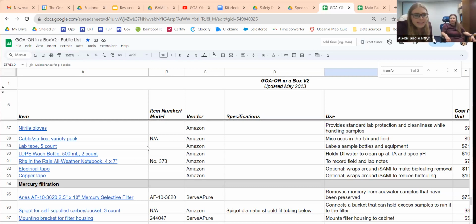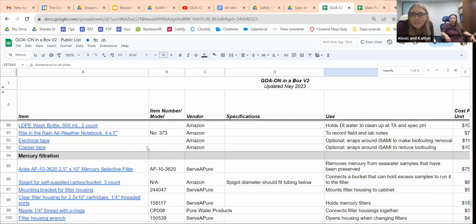Cool. And then the very last thing we're going to chat about is the mercury filtration system. This is the system that you'll set up to deal with the remnants of your samples in the lab after you've done the total alkalinity and the spec pH, when you may have still a little bit in your bottle sample. That can be poured into a carboy, which we haven't supplied, but we have the taps. So you can drill a little hole in a bucket, put your tap in there, and then connect tubing. This will just connect to a bucket and seal really well.